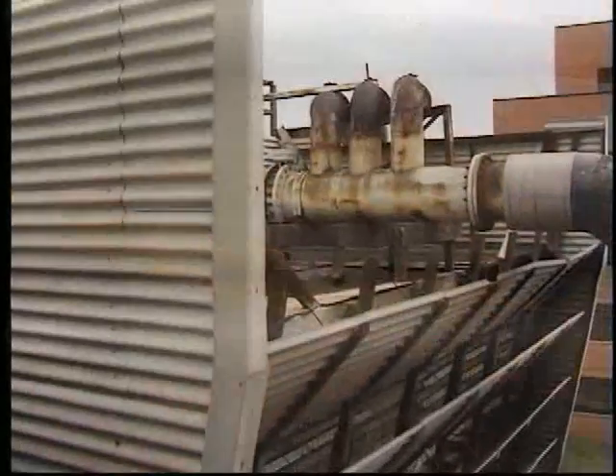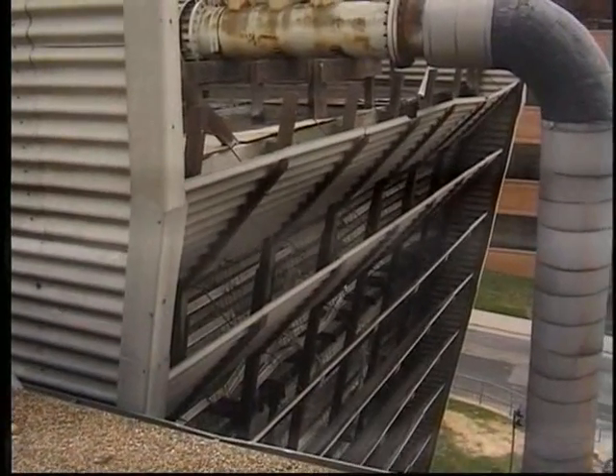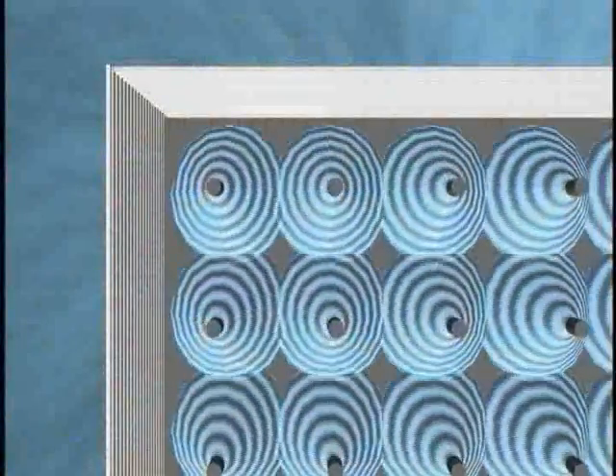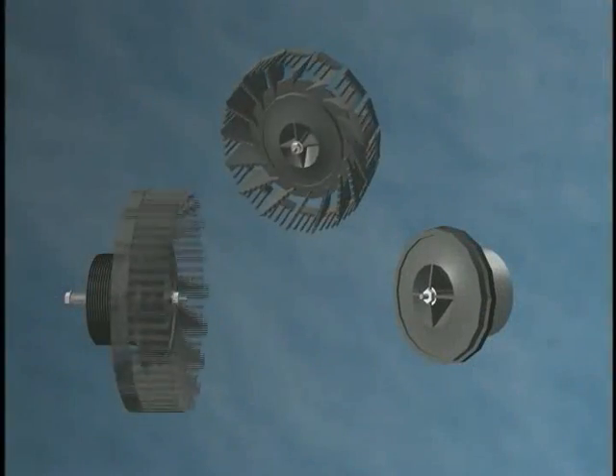many are used. What's more, conventional towers are designed around a single water flow operating point and pressure to achieve operating efficiency. Because they contain fixed orifice nozzles, reducing water flow or operating pressure causes their spray patterns to shrink, which opens up dry voids in the fill media for air to escape without doing effective cooling.